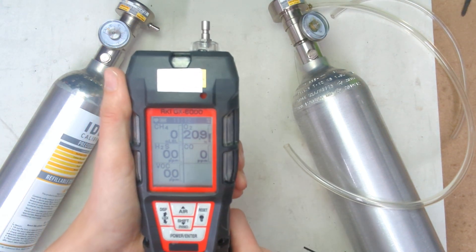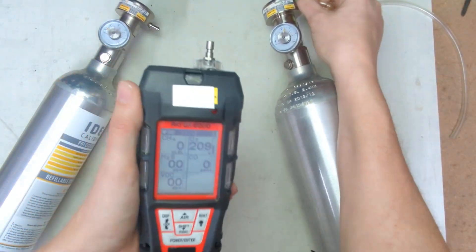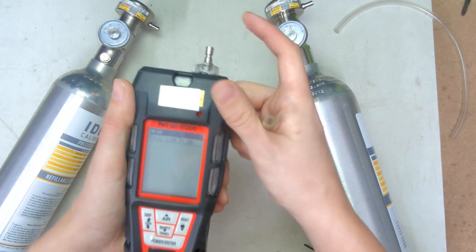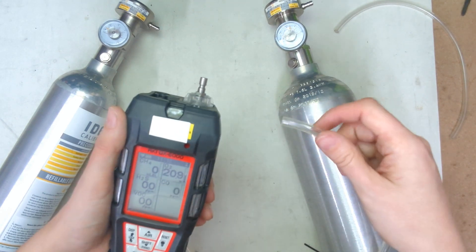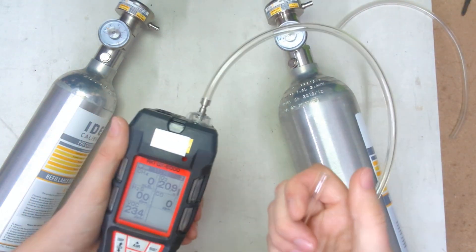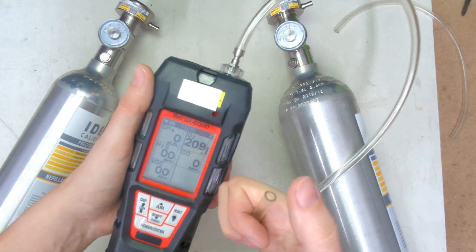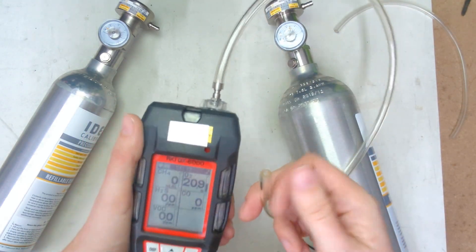There's one more check you want to do before you go in the field each day, and that is a pump check. What you want to do is take your line here, and when you start it up, it's good to check the pump independently. Just do it like this — wait for the alarm. It says low flow — good. That means the pump's working properly and there are no leaks internally. Once you have your tubing set up for a sample, put everything together, and then at the very end of your sample line — whether it's 10 feet, 25 feet, whatever it is — take your thumb and put it over the end of the line. It might take a couple seconds to fail. You want to do that check every day before you go into the field to make sure there are no leaks, because if there are leaks, they'll dilute your sample and you won't know what's in the room.